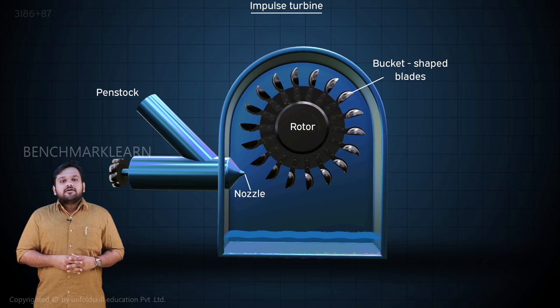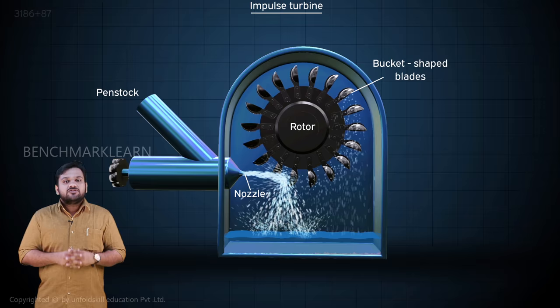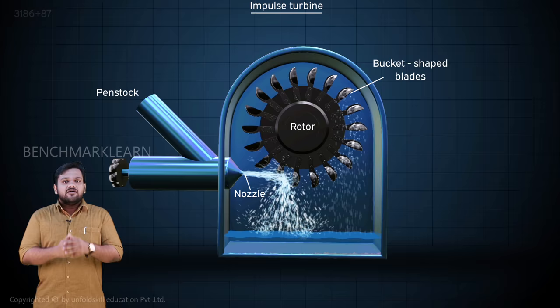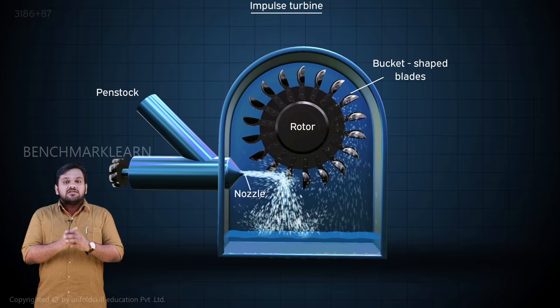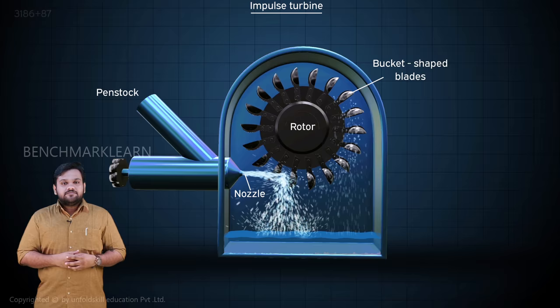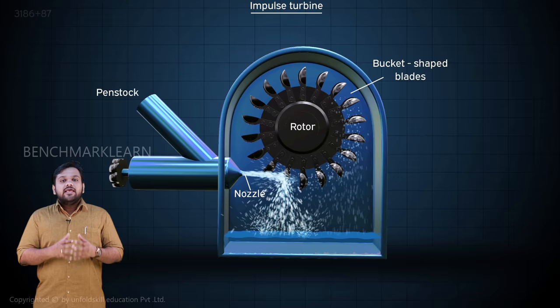This water, when it strikes the curved surface of the bucket, imparts its energy to the bucket, which in turn results in the rotation of the bucket. Due to the curvature of the bucket, the direction of the water jet is almost reversed to get maximum force. This reversal is by about 165 degrees. The flow rate of water controlled at the nozzle helps in determining the speed and power generated at the rotor.